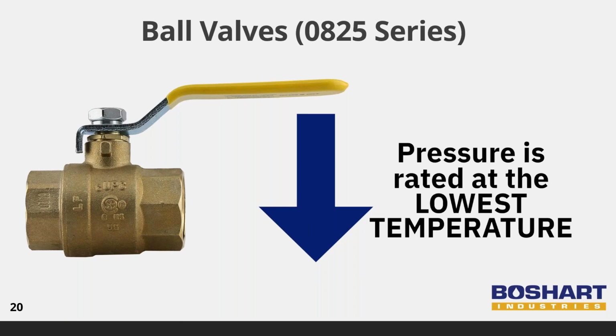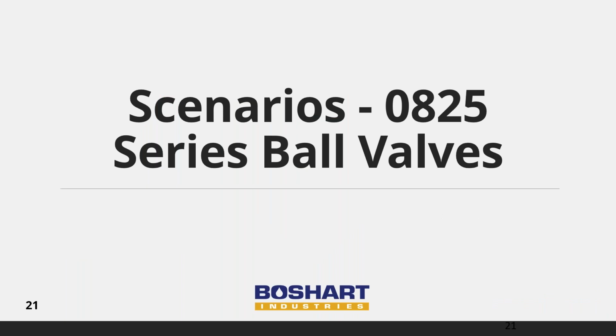We will walk through a couple of ball valve scenarios looking at the Boshart 0825 series. It is important to note that there is not an industry temperature pressure derating chart for valves. You must obtain the chart from the manufacturer. Let's move on to some ball valve scenarios.